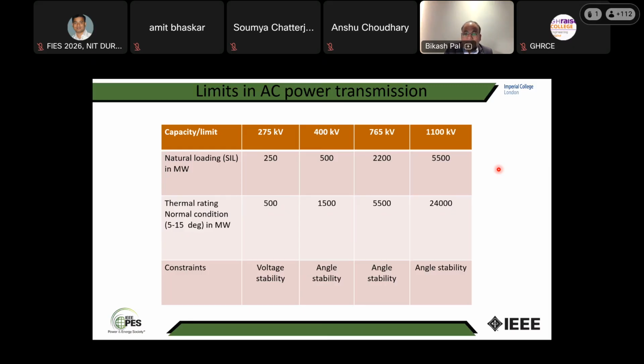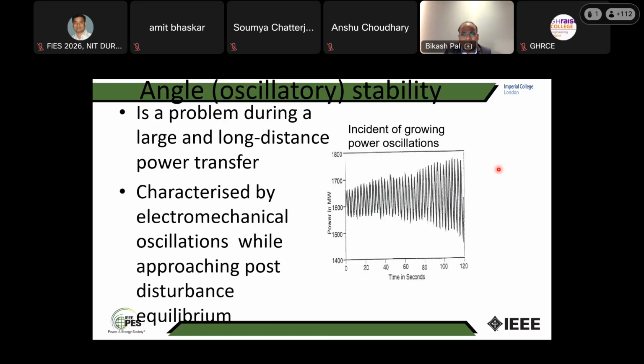And then when angle stability or voltage stability problems manifest, what is the nature of that manifestation? The nature of the manifestation is oscillation in the power line. How does that oscillation come? If there is a small disturbance, such as a change in load, that load change will lead to power oscillation in the line. What is this power oscillation? We are talking about RMS power in megawatts, so that is VI cos phi. V is the RMS value, I is the RMS value, cos phi is a number. So where do we get this oscillation? This is a very low frequency oscillation, less than 2 Hz.